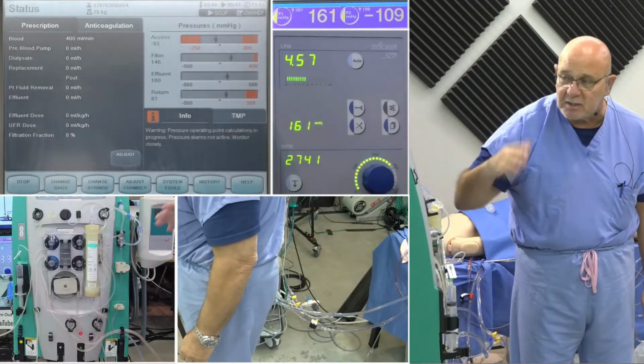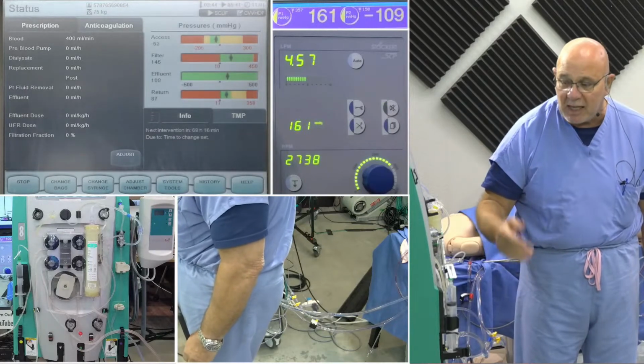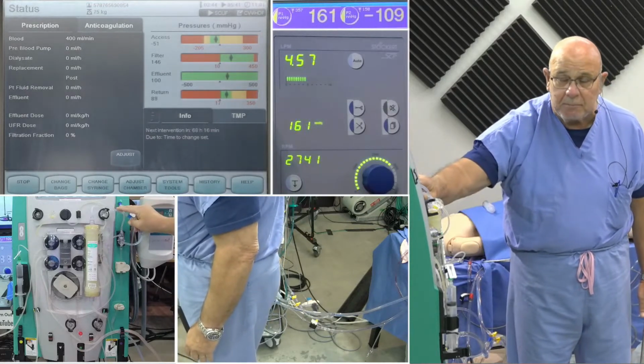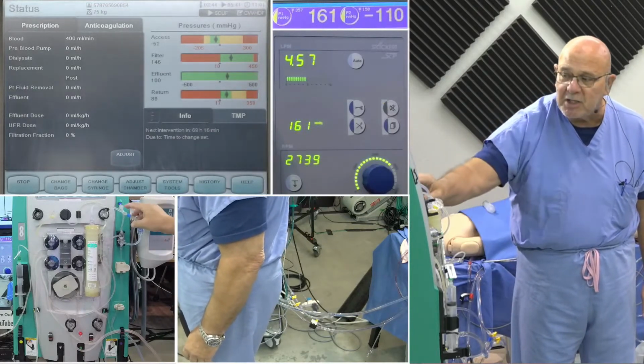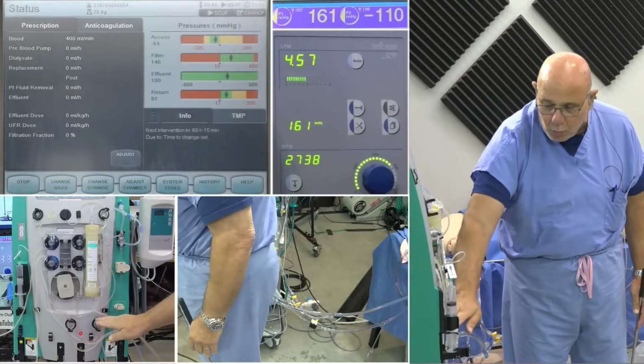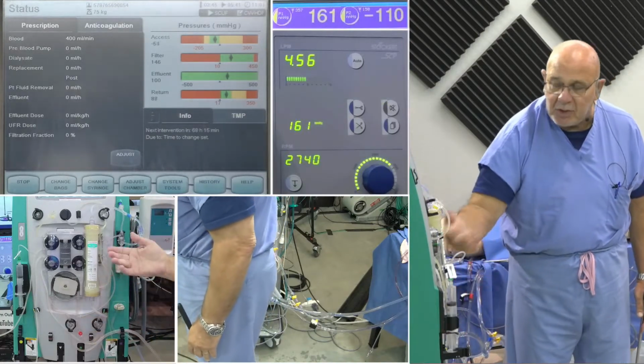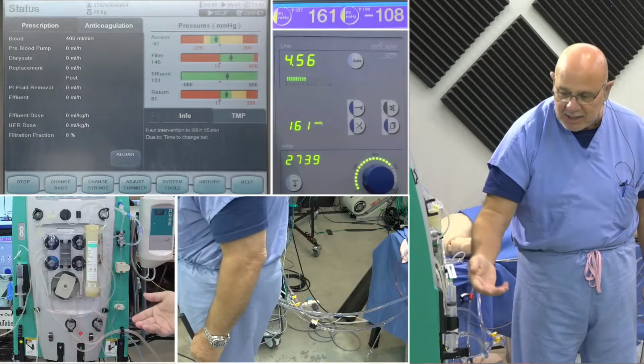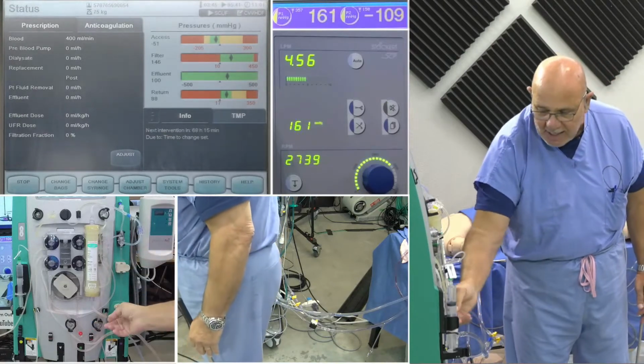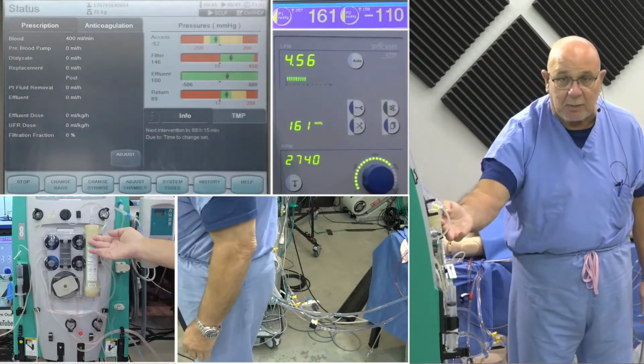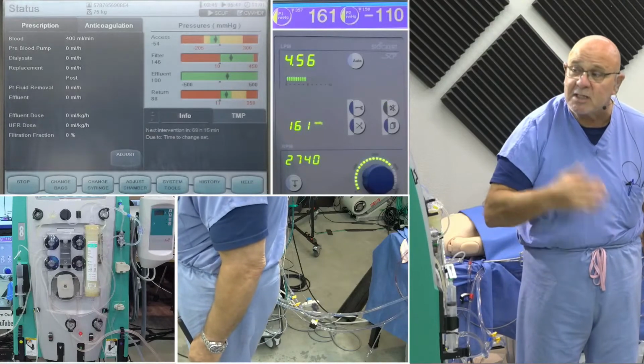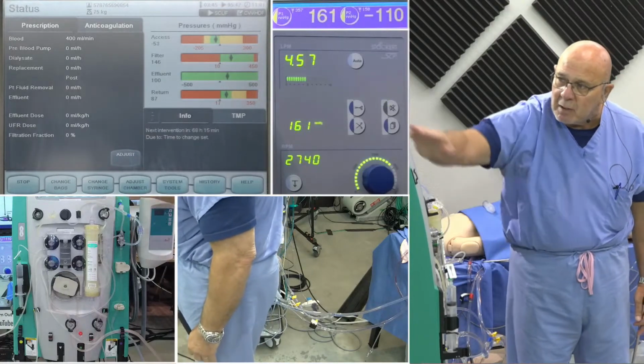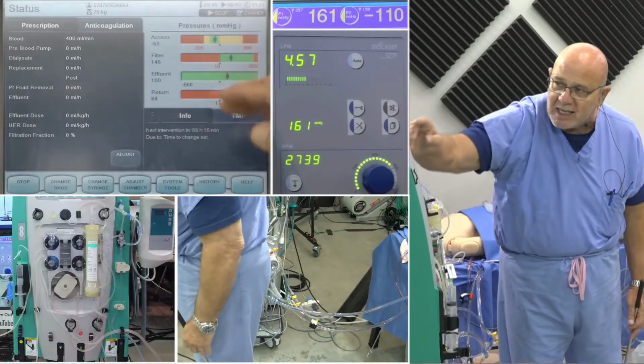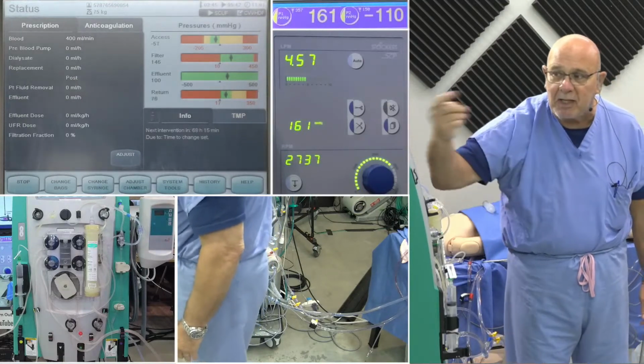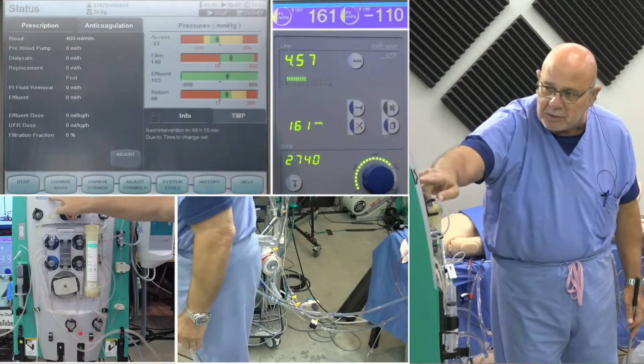That's what it's for, is replacement fluid, either post-filter, which is preferred because you maximize clearance, or pre-filter if you're having anticoagulation issues or coagulation issues and you want to pre-dilute it before it comes through, but that decreases your clearance quite a bit, right? But I want you to watch these pressures as I add replacement post-filter.